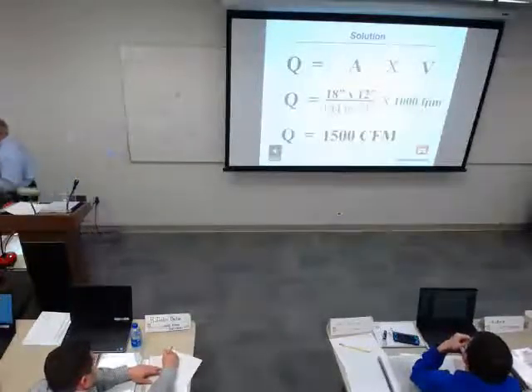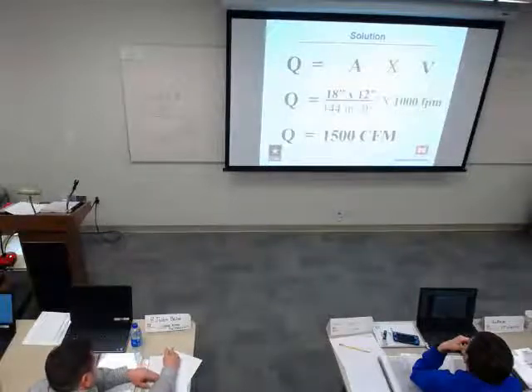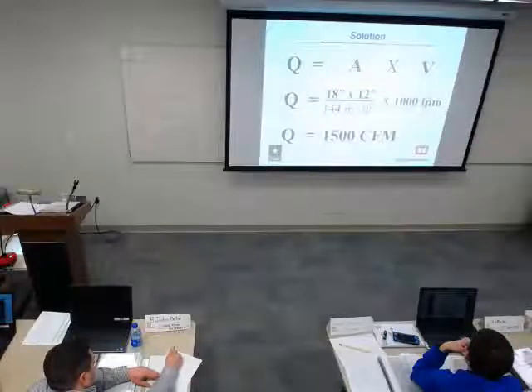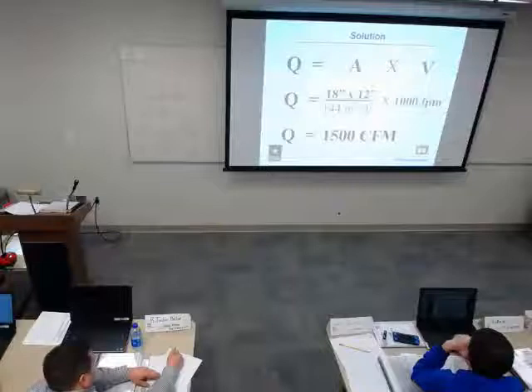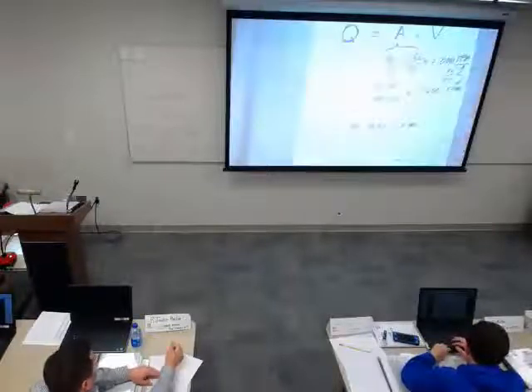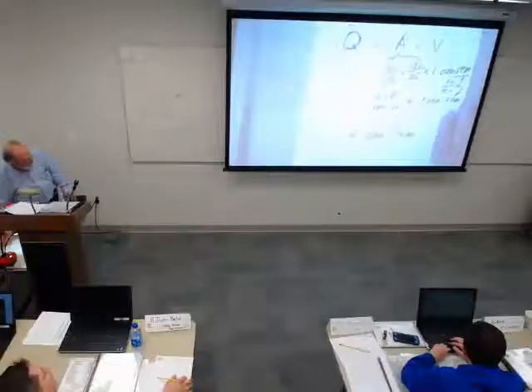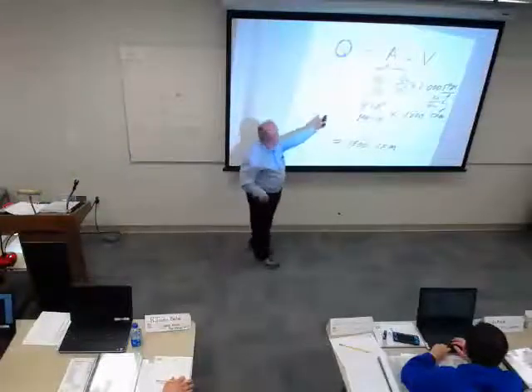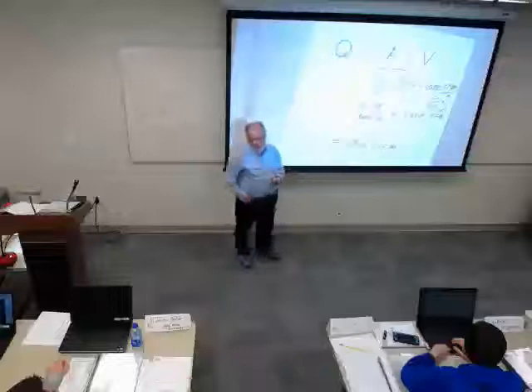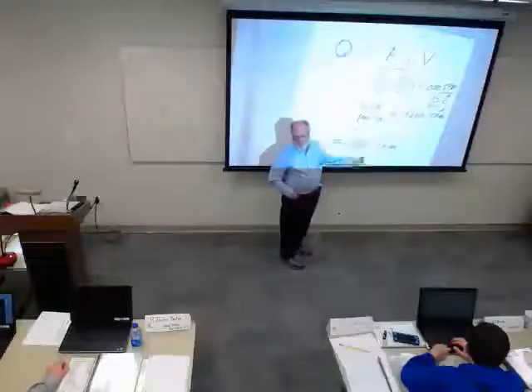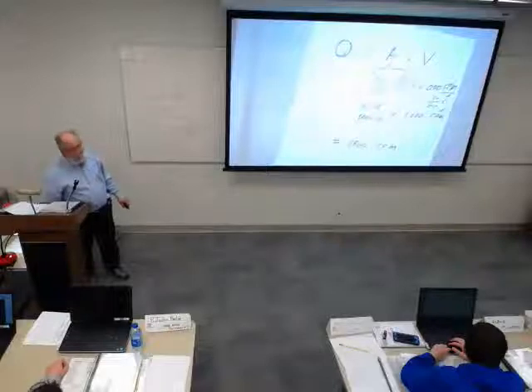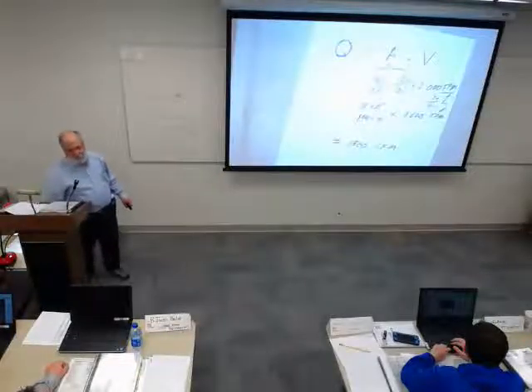I'm going to switch over here to something that used to just drive me nuts. Things like that 144. Where did that 144 come from? Our area is 18 inches by 12 inches. So 18 inches by 12 inches, 12 inches by 12 inches. When you multiply these two 12s on the bottom together, you get that 144. Sometimes that makes it easier to remember. But basically what you do is you convert the duct dimension from inches to feet, and use that square feet number to multiply times your feet per minute, to get your answer in cubic feet per minute.